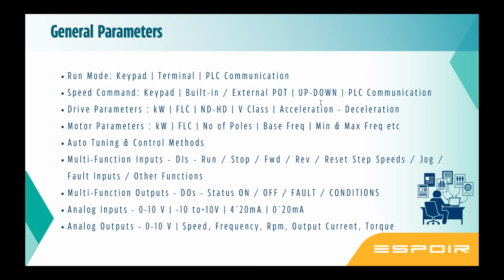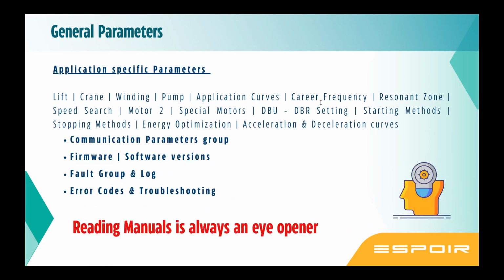So don't ignore this with a few parameters set and the motor starts running. Okay, the motor is running, it started, why should I bother? No, you need to go through every aspect and ensure all the parameters are set as per the application demand, not just by the factory default. There are application specific parameters available as application macros in some brands, and in some brands they are separate parameters. You need to go physically and set all that, like lift, crane, winding, pump.